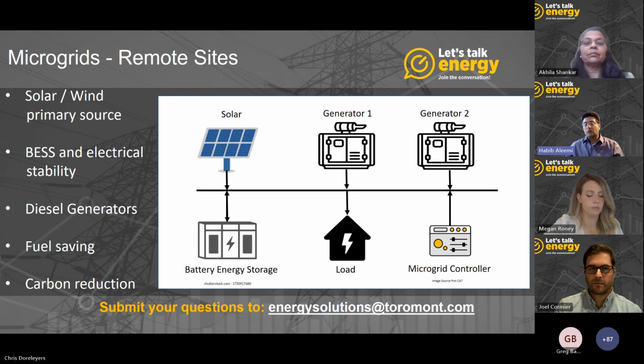BESS, battery bank system, and solar are connected to the bus, with the solar being the primary source of power in the system to energize the load. If there is a bad day, and solar cannot produce enough energy, the battery bank would contribute to the load. When the load decreases, the solar system could recharge the batteries and provide power to the load. If there is a day that solar and battery banks are energizing the load and the charge of the battery drops to 80%, the microgrid controller will start one of the generators or both generators, depending on how much load is available in the system.